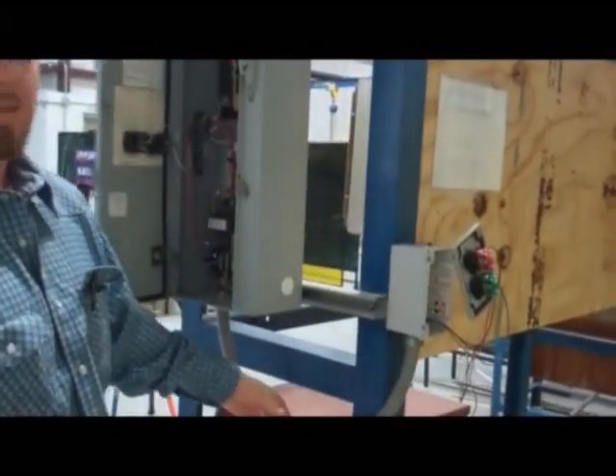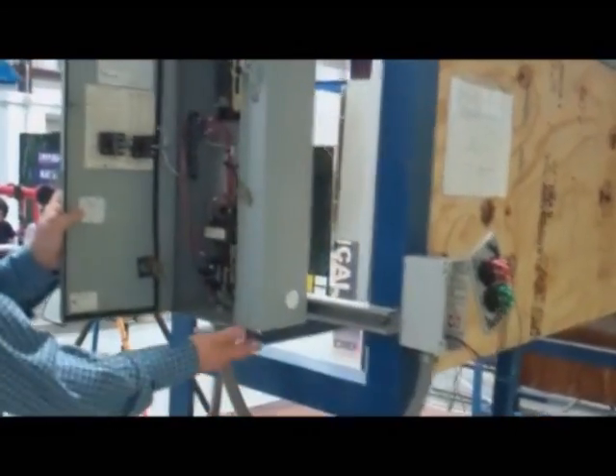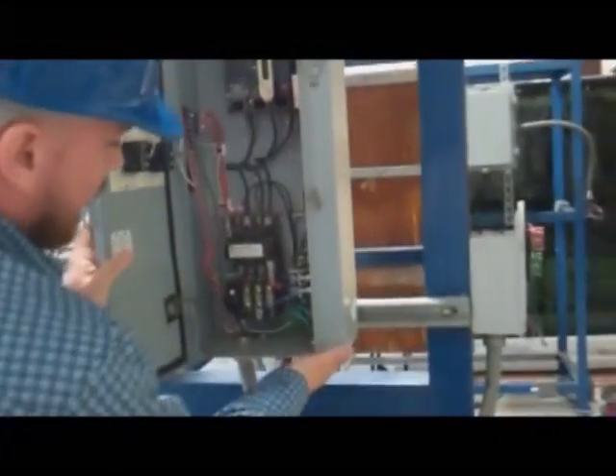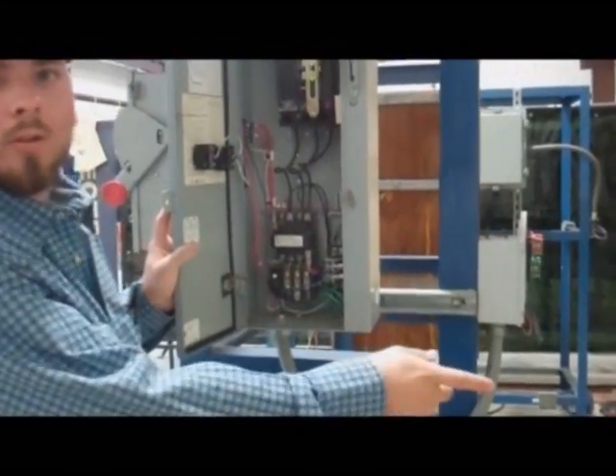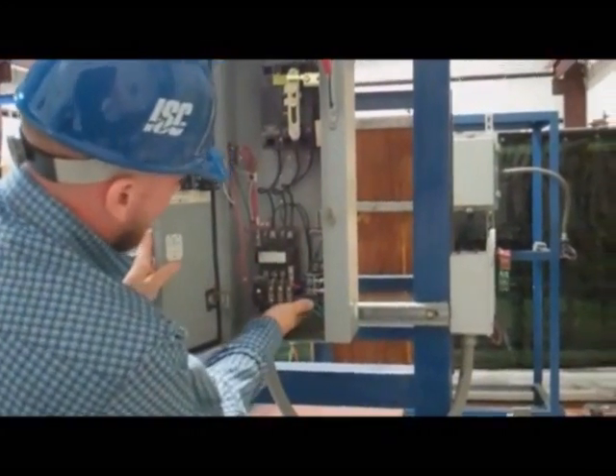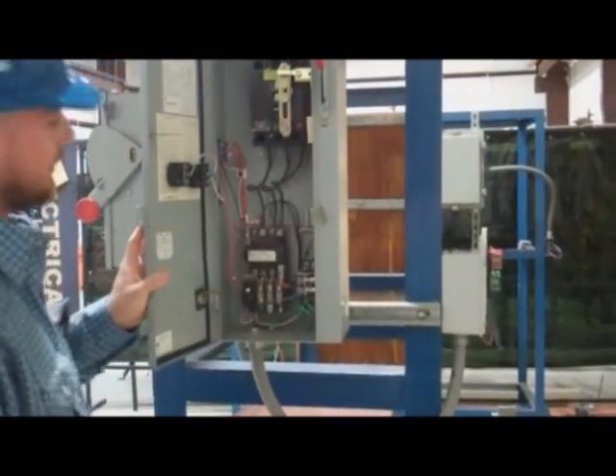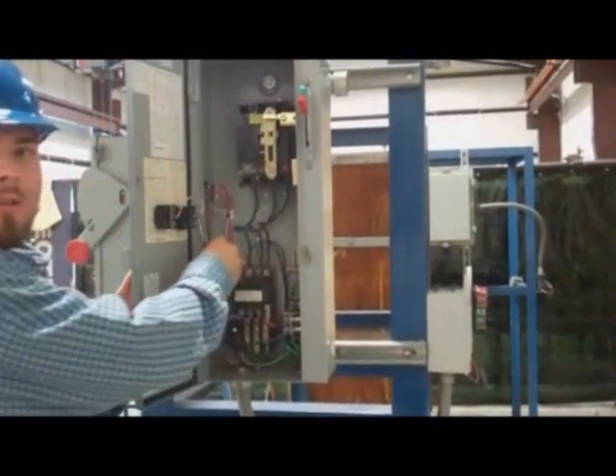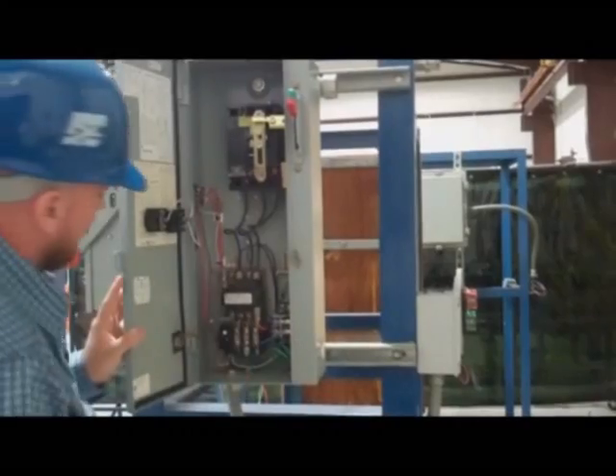This will be a starter. You'll find this inside the MCCs. This is the bucket. If we're in a refinery, in this hole right here, you would have your leads going to your motor outside. They come to the bottom of your breaker. These are our wires going for our start-stop. These are control wiring on the side of the box.